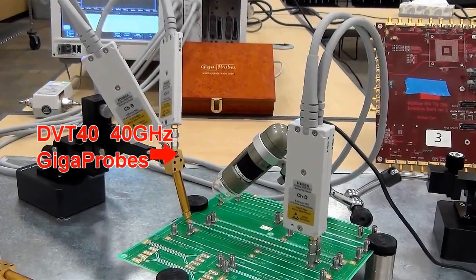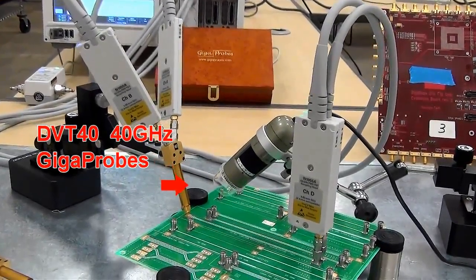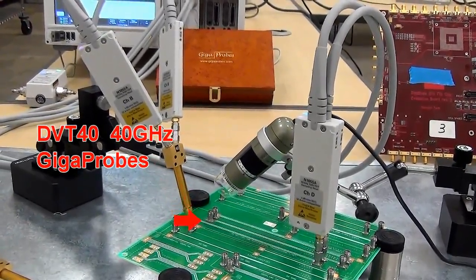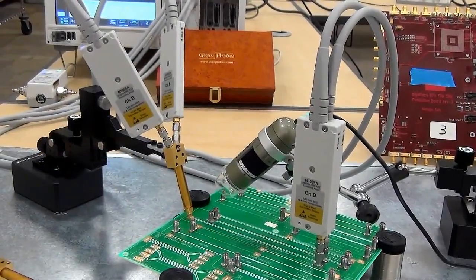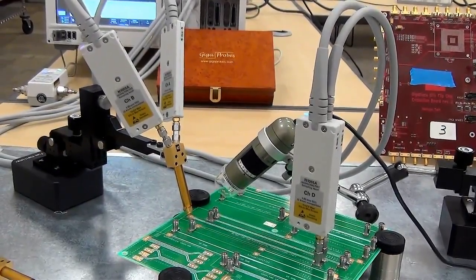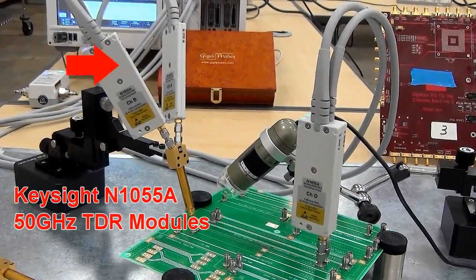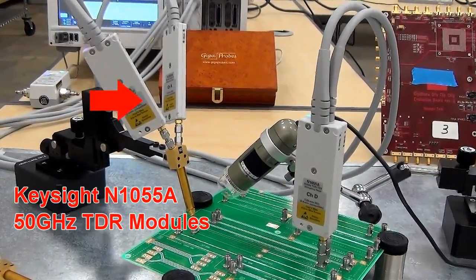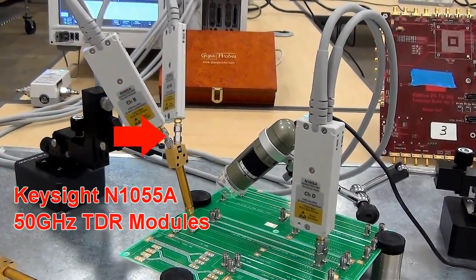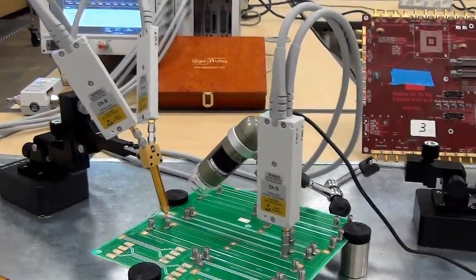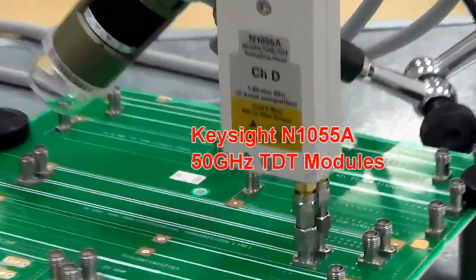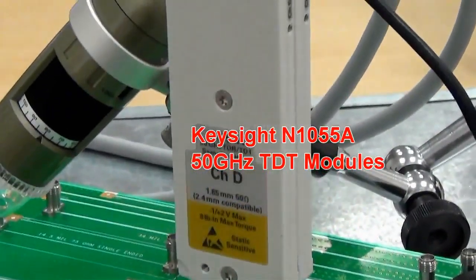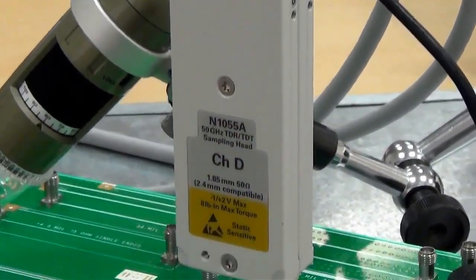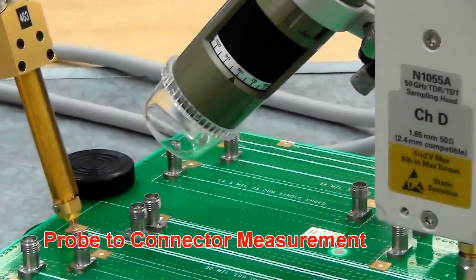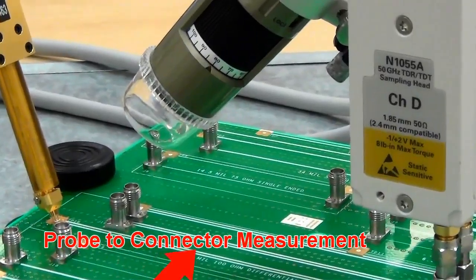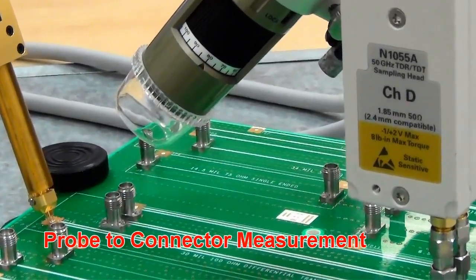Now on the left-hand side we have the differential DVT40s connected to a set of manipulators. We have the 50 gigahertz TDR modules directly connected to the probe, and then on the opposite end of our trace there we have the other set of TDR modules connected to the connectors. So we're going to be characterizing and making impedance and S-parameter measurements of that differential trace.